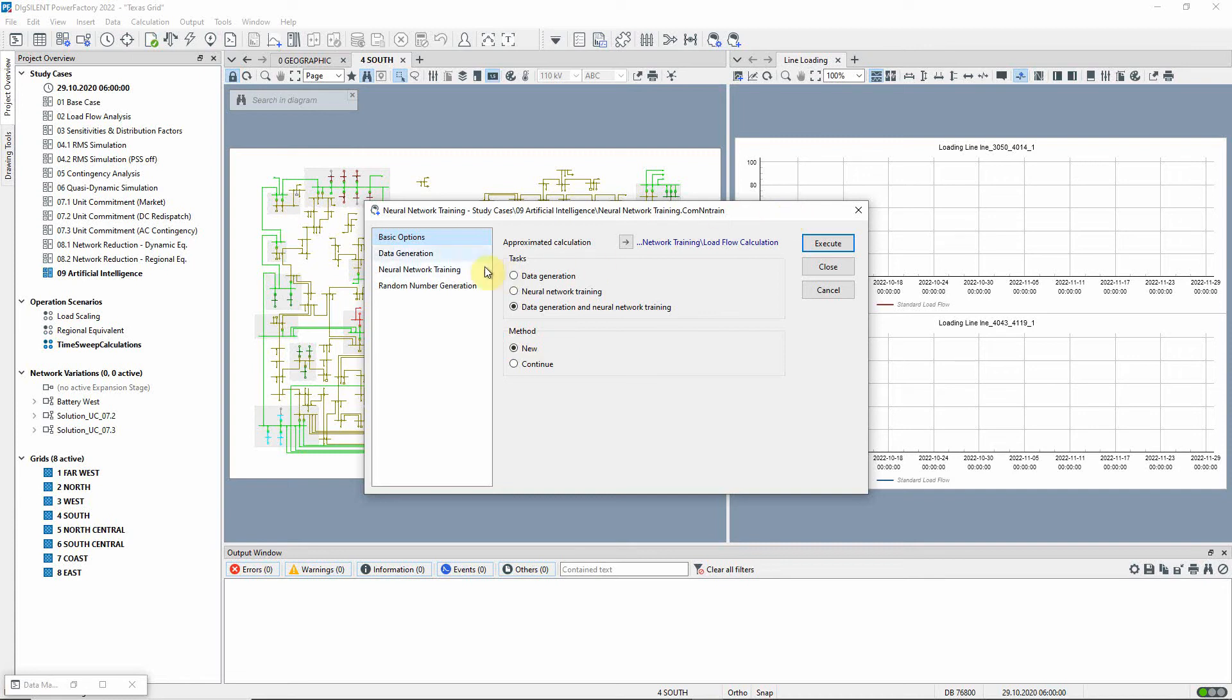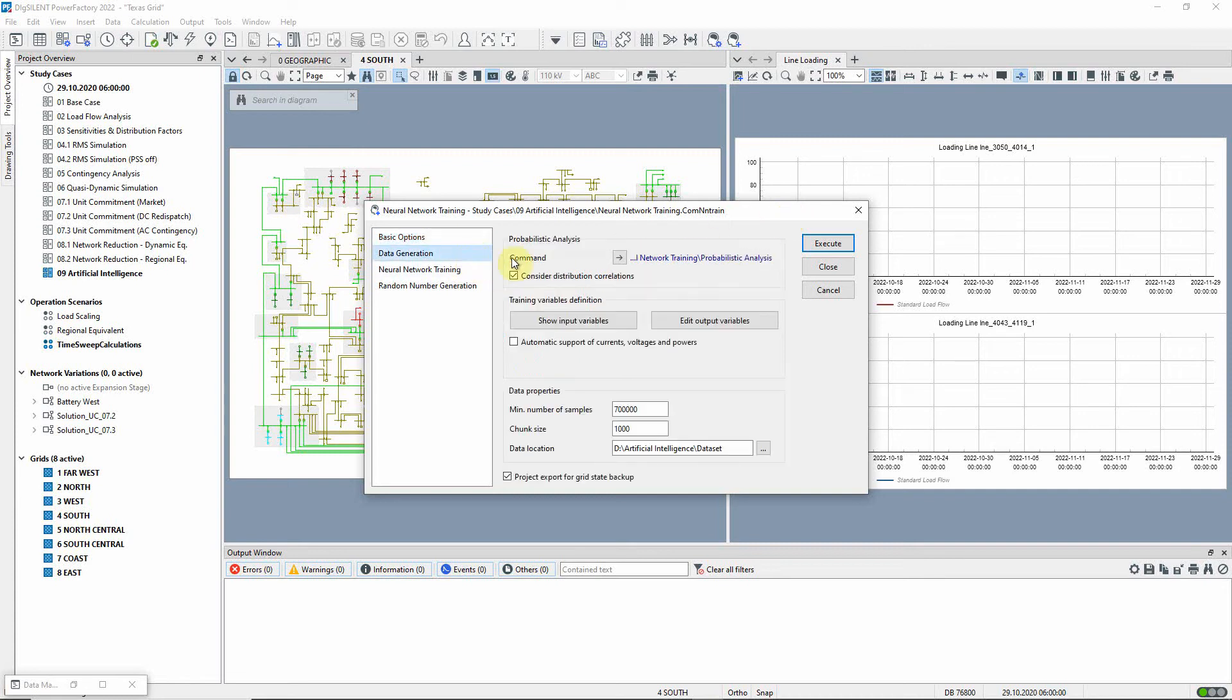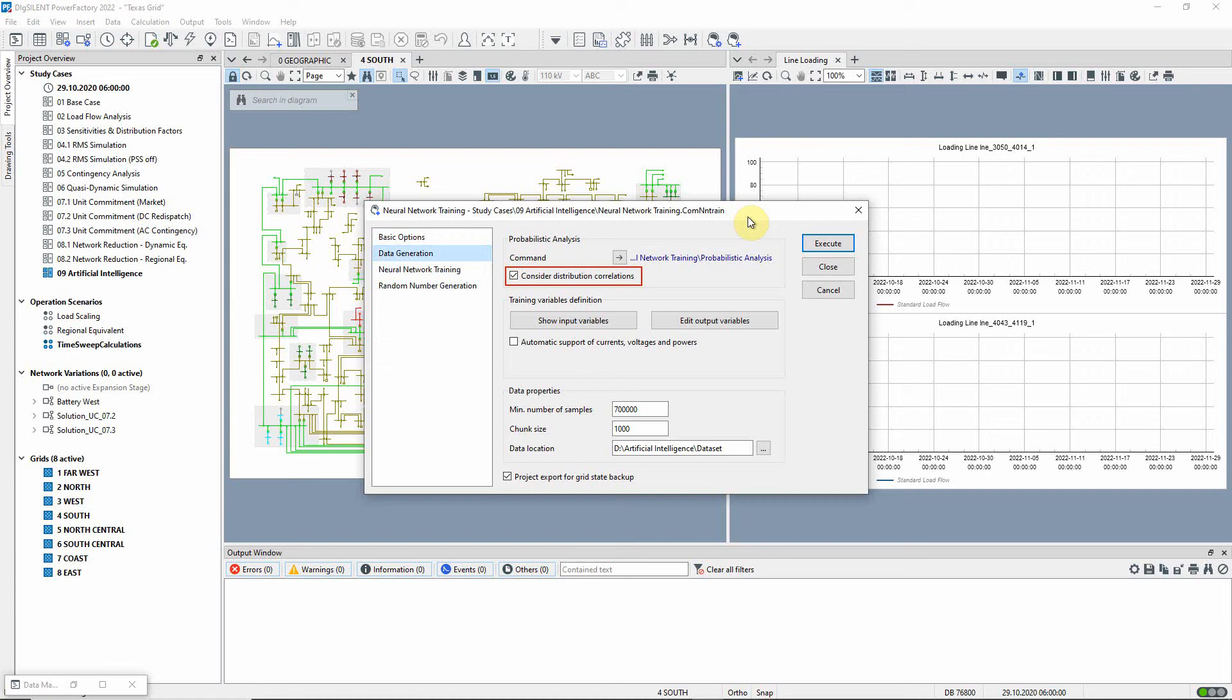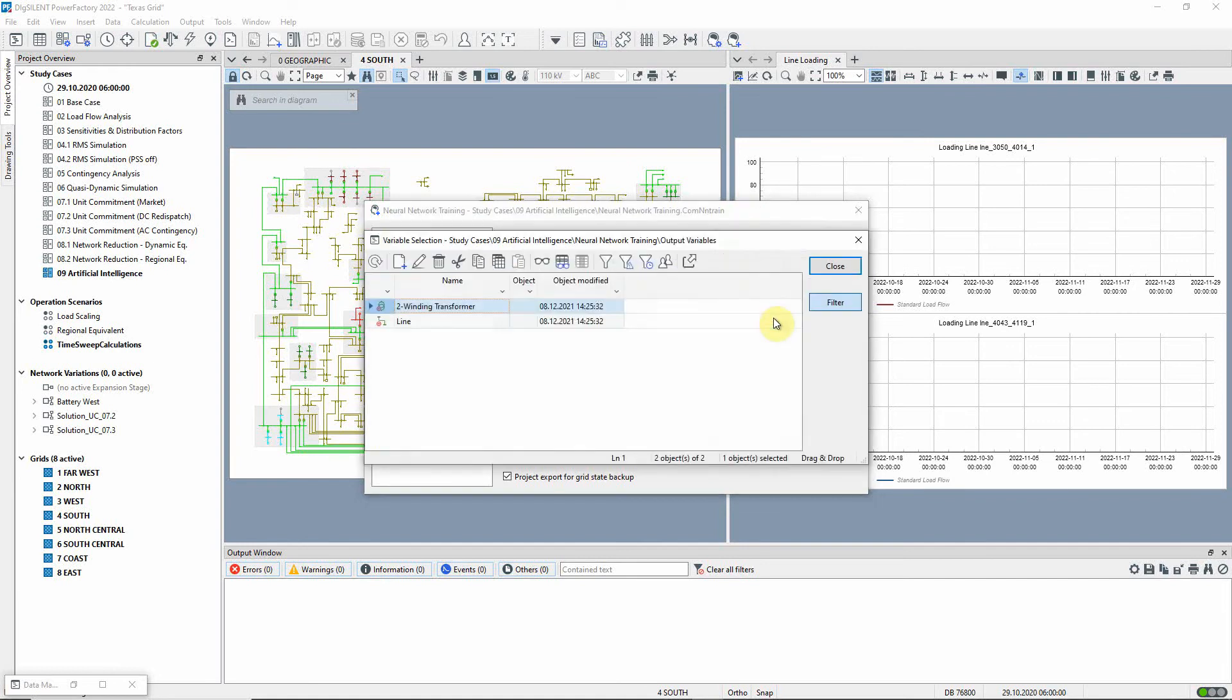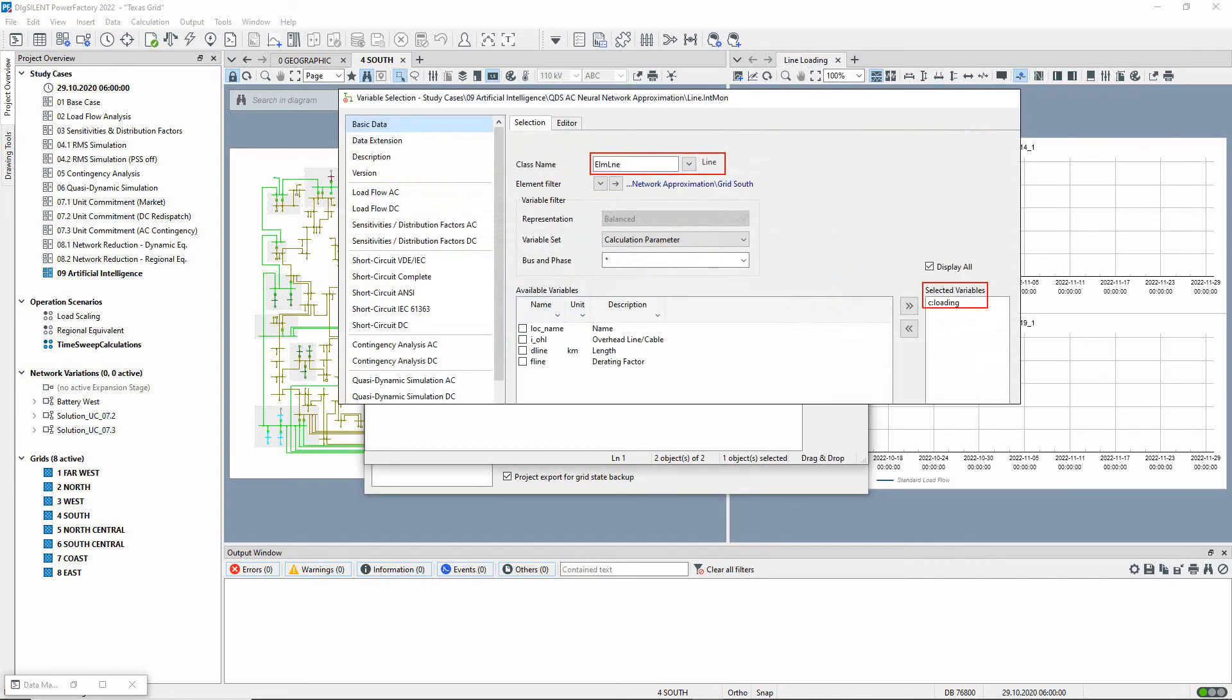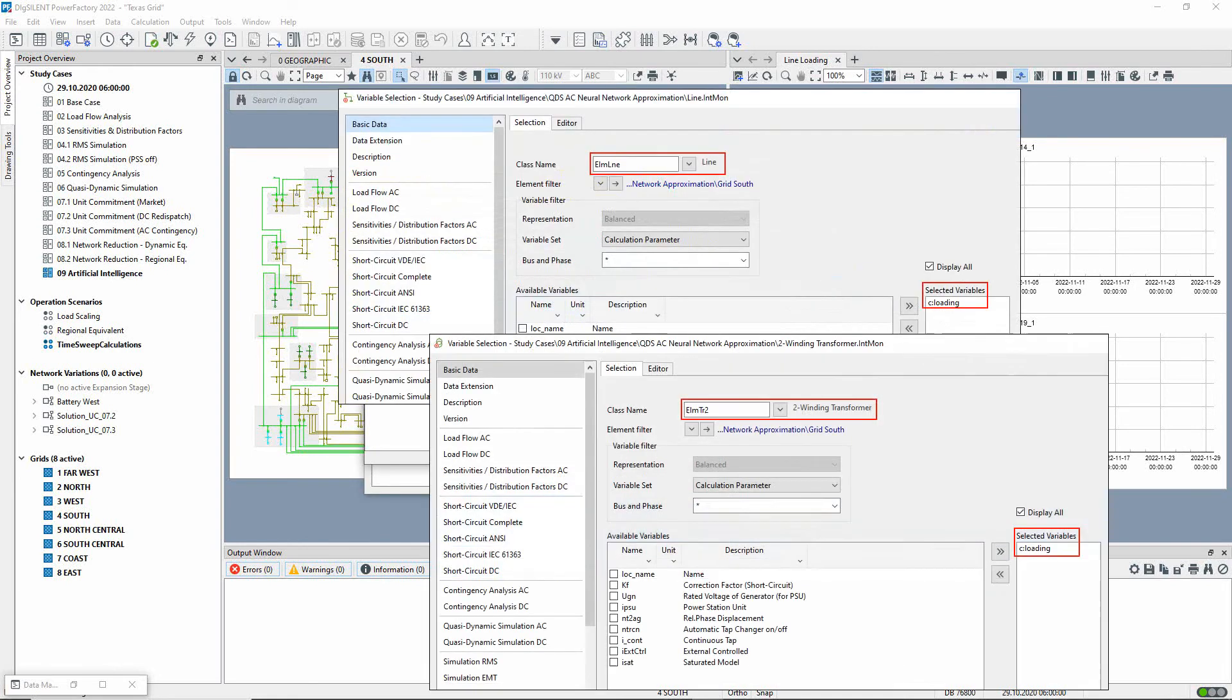On the data generation page, there is a link to the probabilistic analysis command that has been used. Distribution correlations are considered in order to model the time-dependent behavior of the loads and generators. The input variables are automatically selected based on the defined distributions. For the output variables, the line and transformer loadings have been selected using a filter to limit the results to those of the south grid.